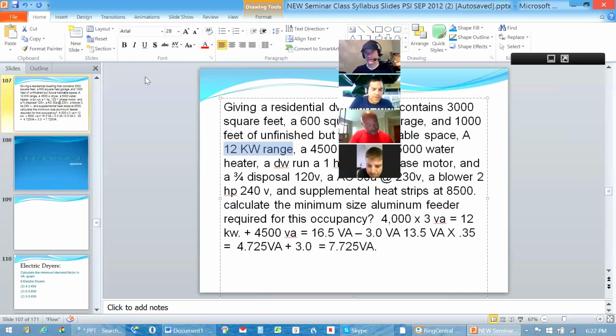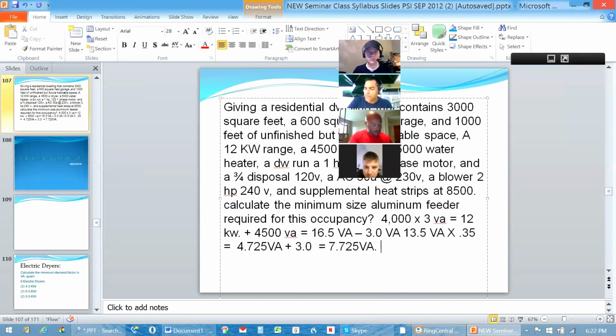There's 8. That's right. So you're just looking at the fact that, first of all, it's a service calculation, and second of all, there's just one of them, so you're on row 1, and of course the size of the range is 12 kW, so it doesn't go past 12, column C, but it's certainly past column B, so it's got one range there at column C on row 1 would be 8,000 watts. So there's really no math involved with that one. You're substituting that 8,000 for the 12 kW, so the 12 kW becomes simply an 8,000 watt value for the demand load. Okay.